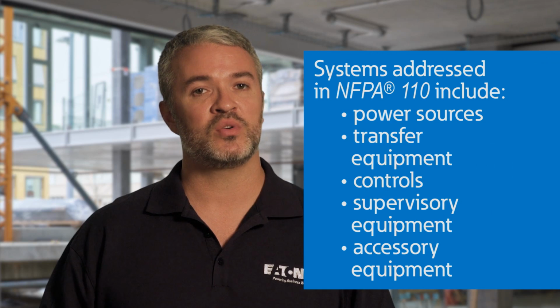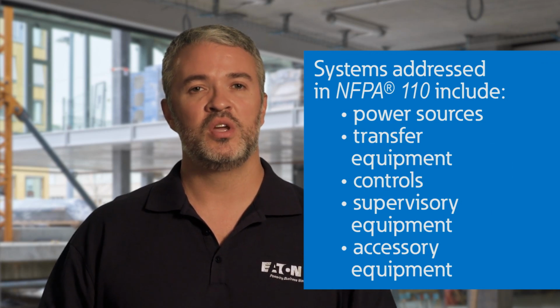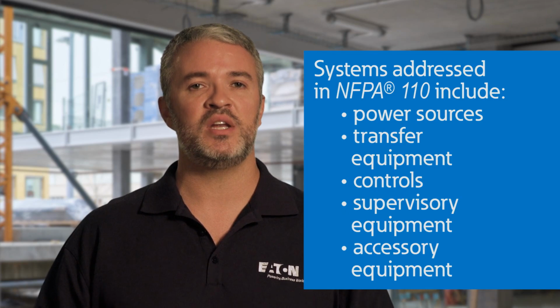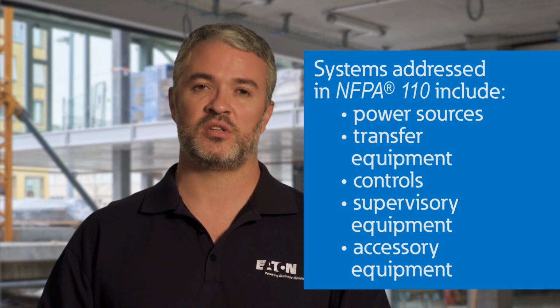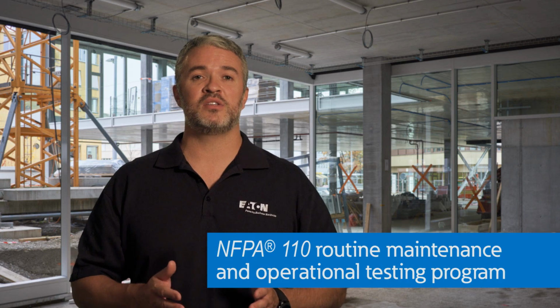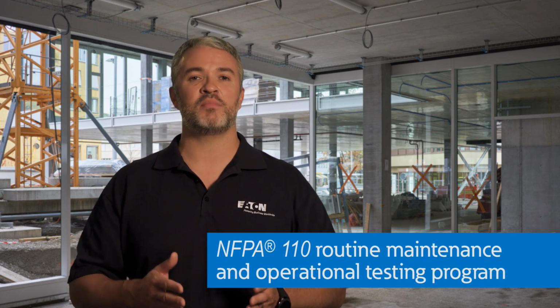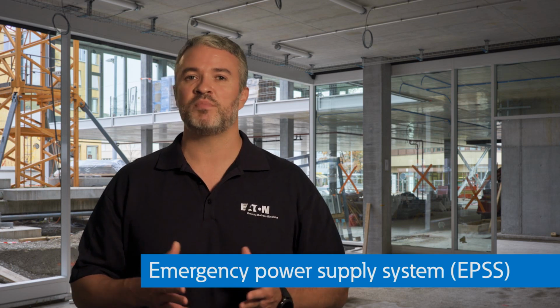In the event that the normal electrical power source fails, transition to backup equipment must occur in a timely and reliable fashion. Systems addressed here include power sources, transfer equipment, controls, supervisory equipment, and accessory equipment needed to supply electrical power to the selected circuits. This code requires a routine maintenance and operational testing program after the standby power system has passed acceptance tests or after completion of repairs that impact the operational reliability of that system. It also requires a defined written schedule for routine maintenance and testing of the emergency power supply system, or EPSS.